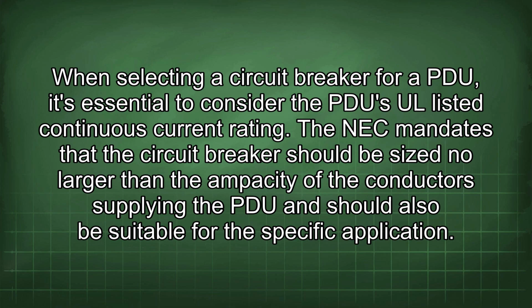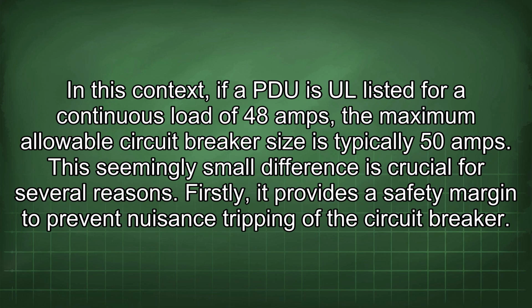When selecting a circuit breaker for a PDU, it's essential to consider the PDU's UL listed continuous current rating. The NEC mandates that the circuit breaker should be sized no larger than the ampacity of the conductors supplying the PDU and should also be suitable for the specific application. In this context, if a PDU is UL listed for a continuous load of 48 amps, the maximum allowable circuit breaker size is typically 50 amps. This seemingly small difference is crucial for several reasons.